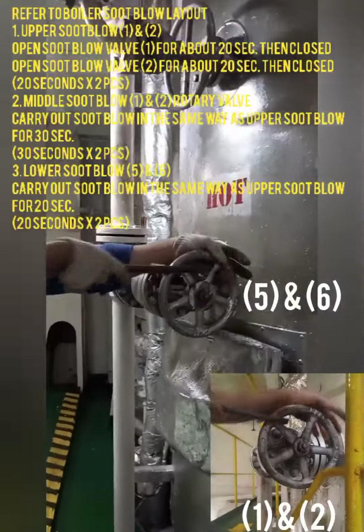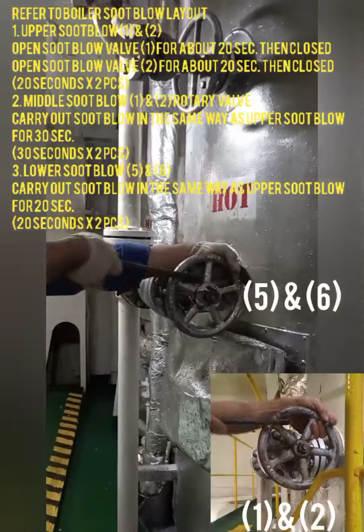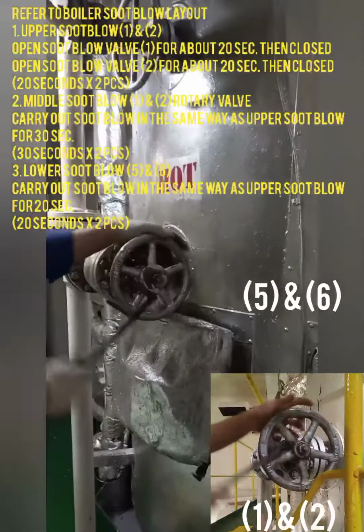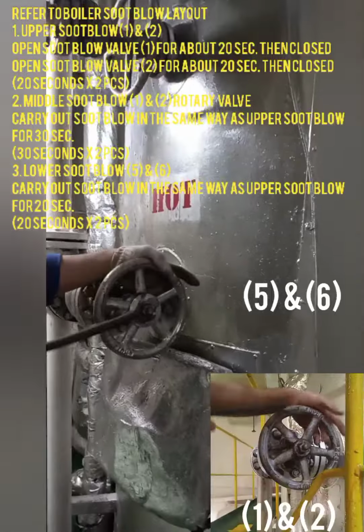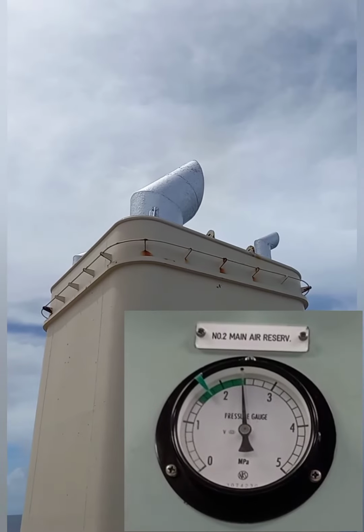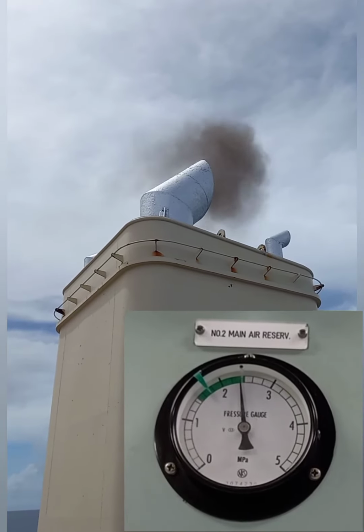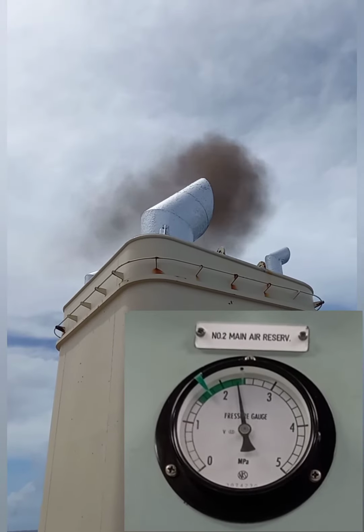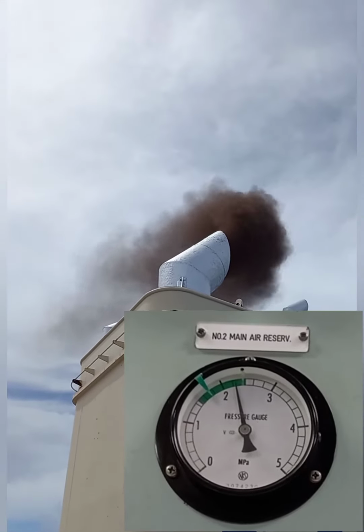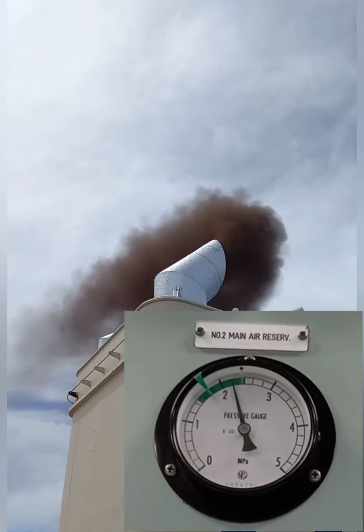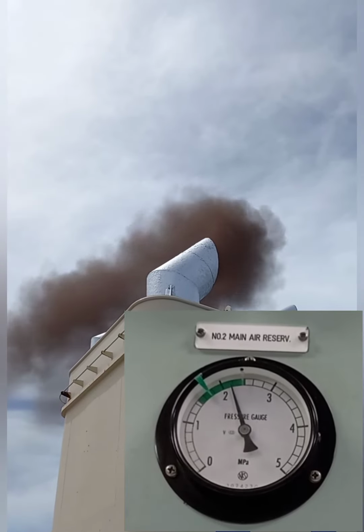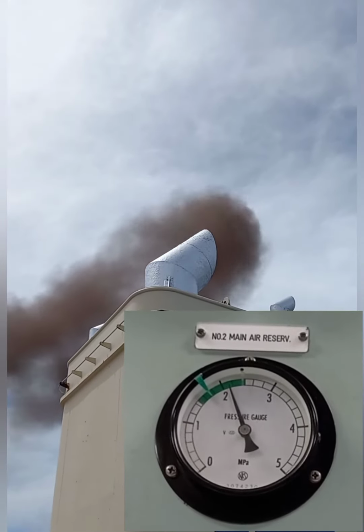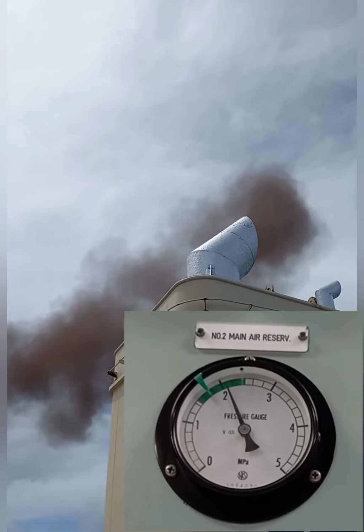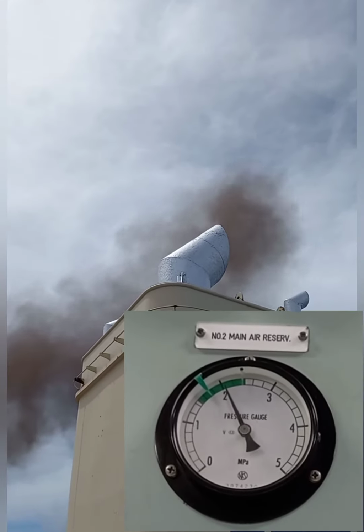Number 3. Carry out soot blow according to the following sequence. When air tank pressure is sufficient, or over about 2.2 MPa, the next operation can be started. If pressure is below about 2.2 MPa, wait until air tank pressure is increased. Start the next operation after making sure that the air tank pressure has returned to the provided pressure.